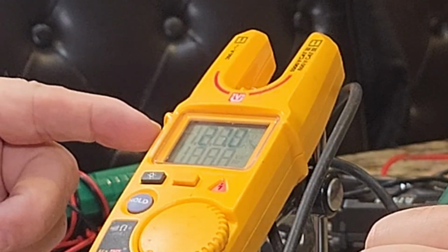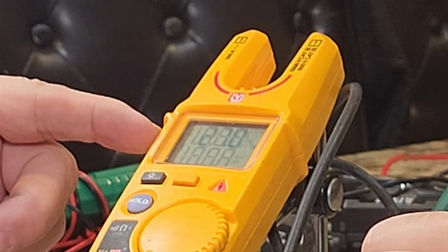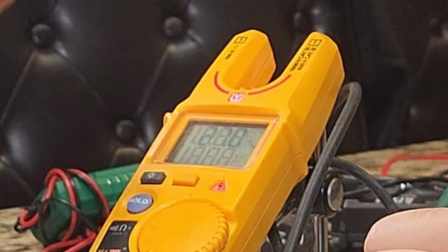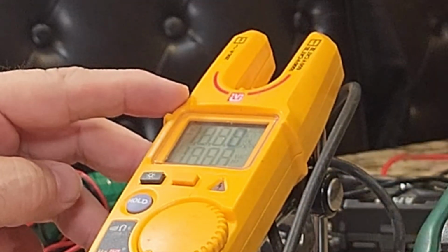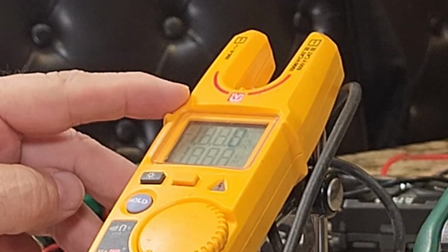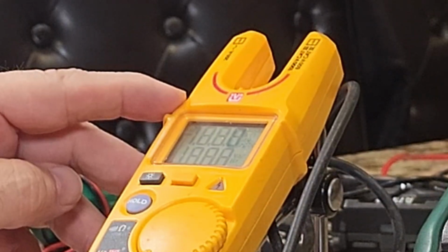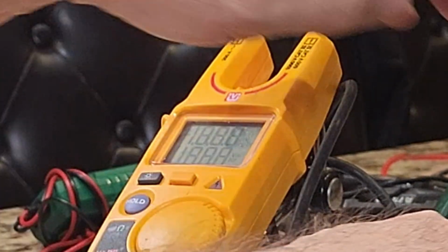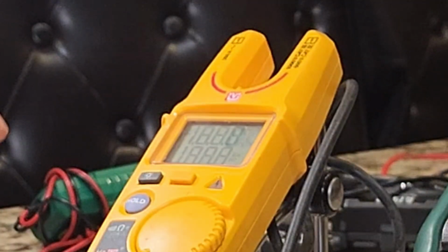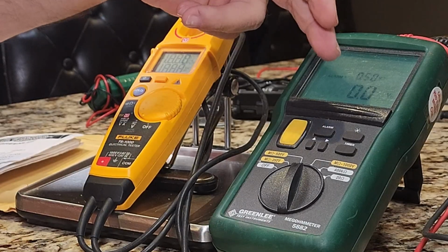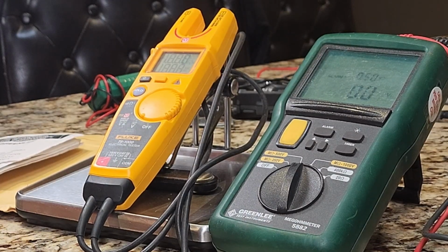And you can see this is 270 volts. And it's at 0.92 megohms. 0.92 was the resistance, right? Yeah. Now let's fire it up to 500 volts. And then again, it's going to look for voltage. It doesn't see any voltage.